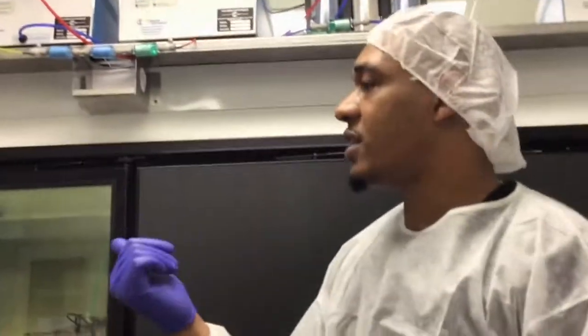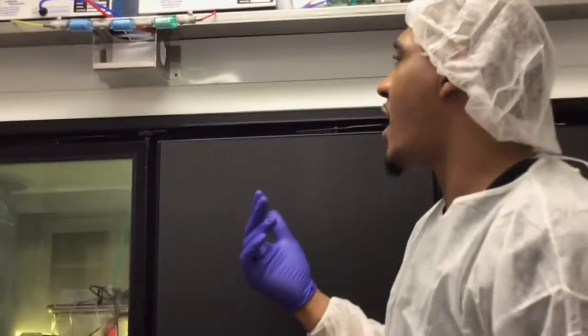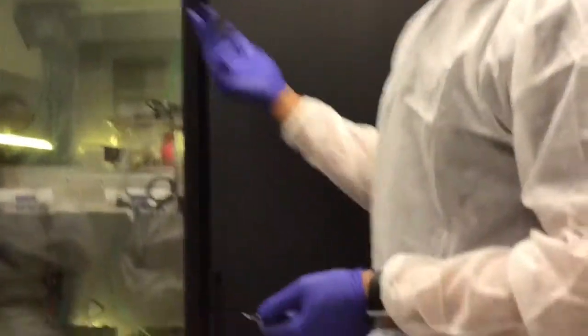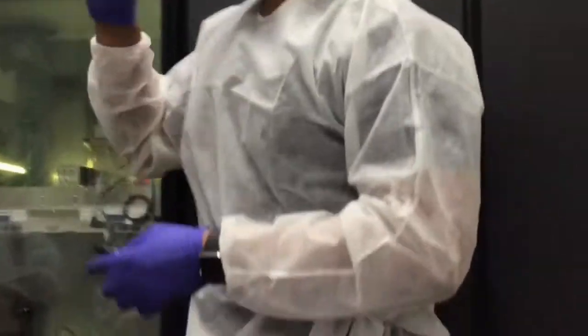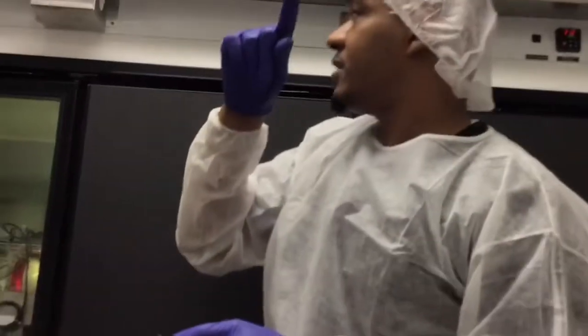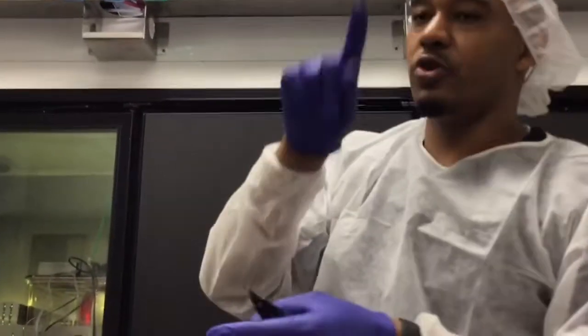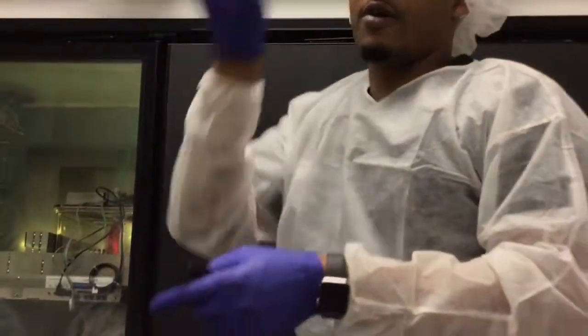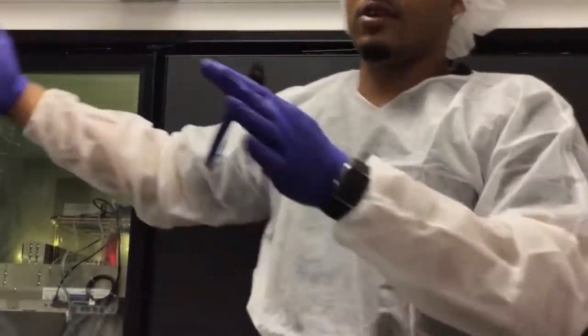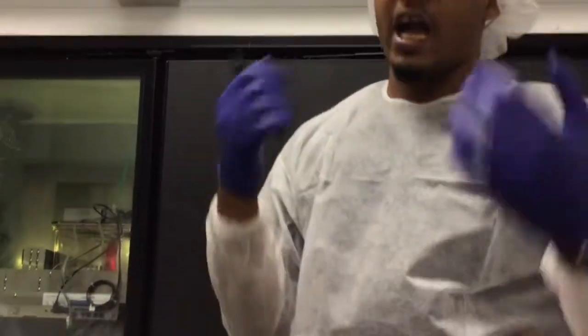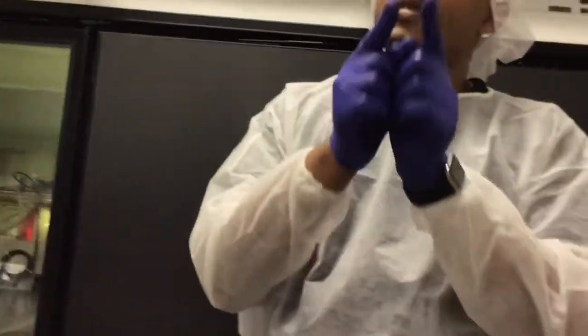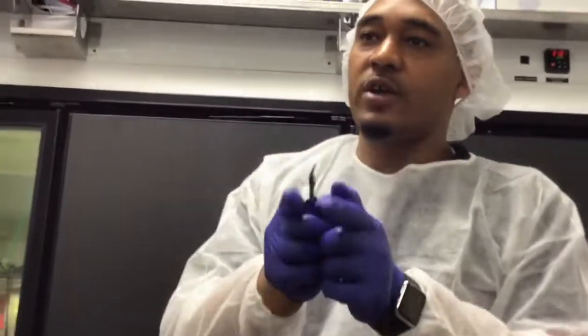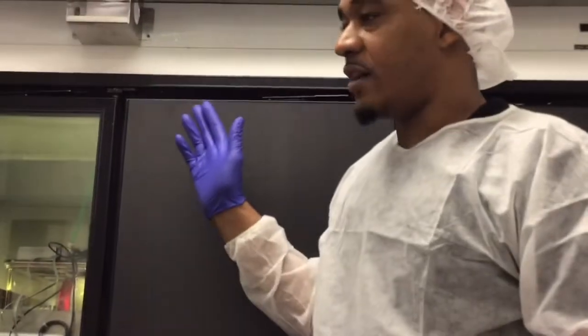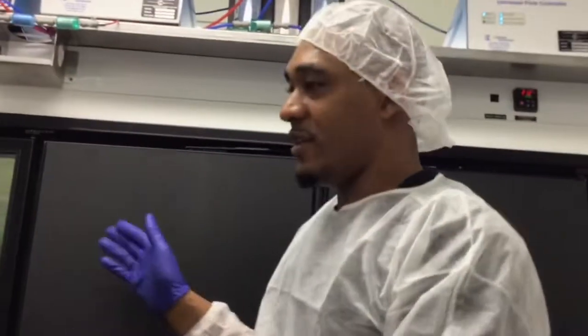So let's say we have a 4-channel experiment. What will happen is that little output multiplexer will only go to 4 channels: 1, 2, 3, 4, come back, 1, 2, 3, 4. So it's not looking at all 8 cages, but all 8 are constantly being sucked by the giant pump. Now it just decides which cage am I looking at and sending the sample. Not rocket science. Very, very easy.